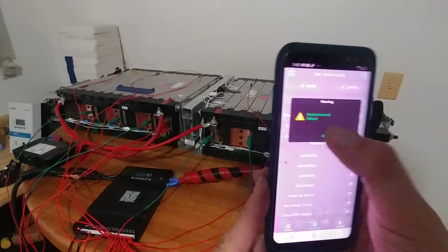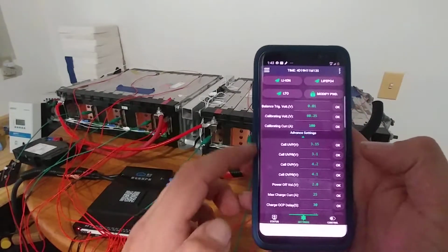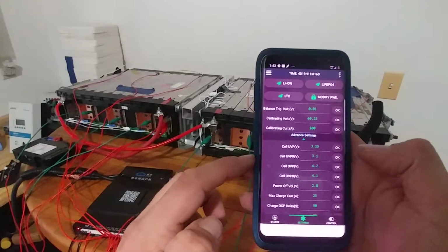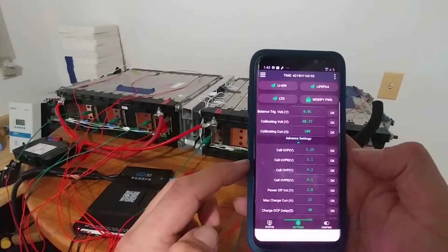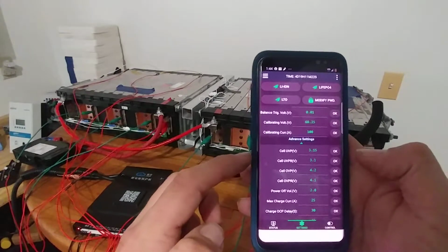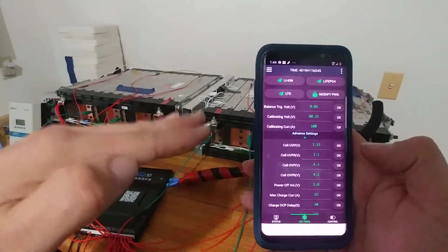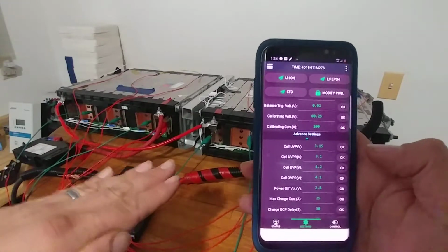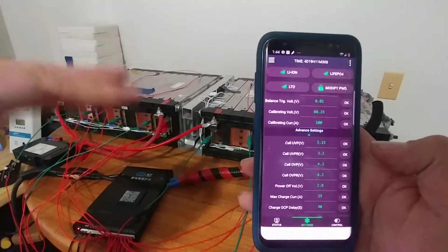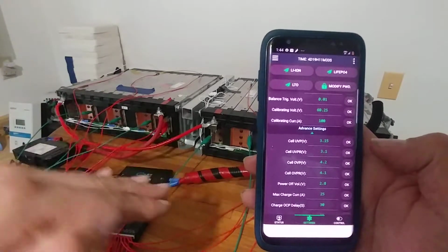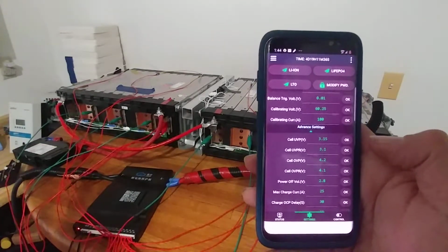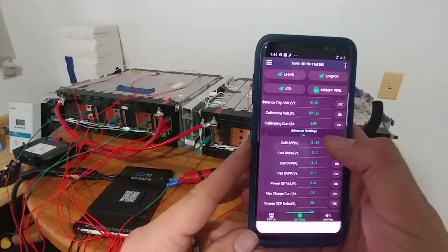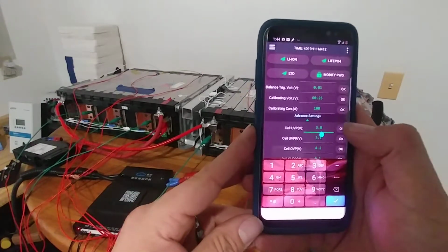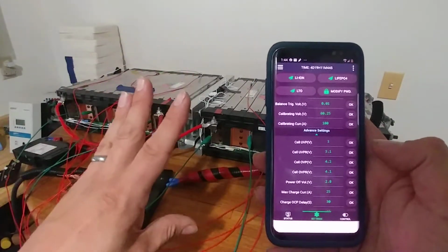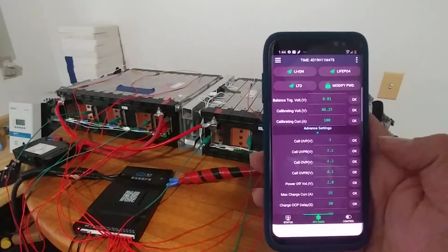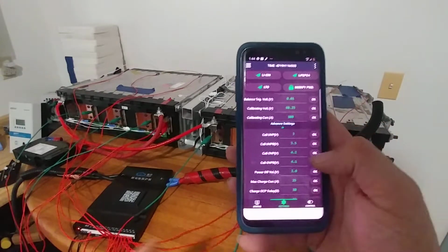And you see that it actually failed. Now the reason for that is this is under voltage protection and under voltage protection recovery. What this means is that under voltage protection would have this thing triggering off at 3.15 and then triggering back on at 3.1. It doesn't work that way. You have to have it trigger on at a higher voltage. The recovery is going to be higher in this case. So the way to do that is to actually set this to 3.0, and then you're going to see it's just going to beep OK because it's a valid setting. So it's not allowing you to do an incorrect setting.